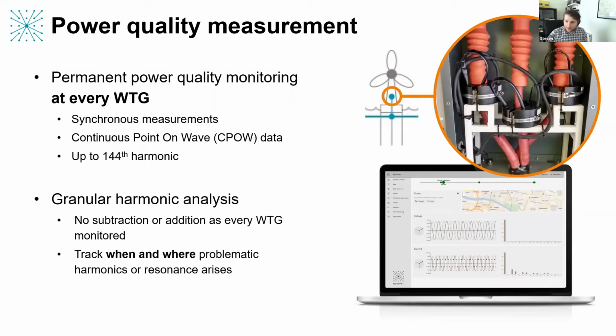And that's very, very powerful. For example, for power quality monitoring, we typically deploy a 14.4 kilohertz sampling rate, which of course will give you about the 144th harmonic in principle. So that's a lot of visibility of the harmonics that are present in the system.